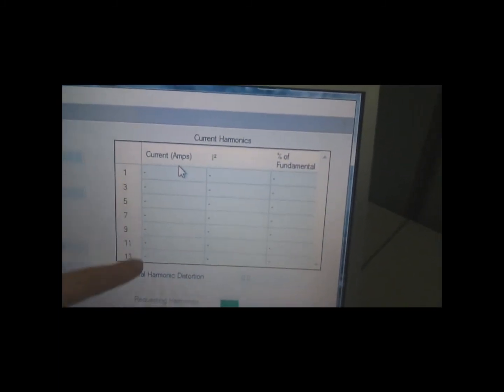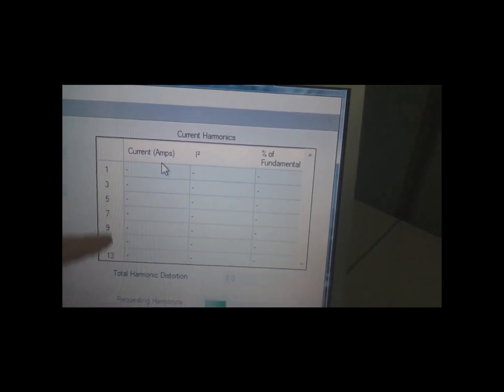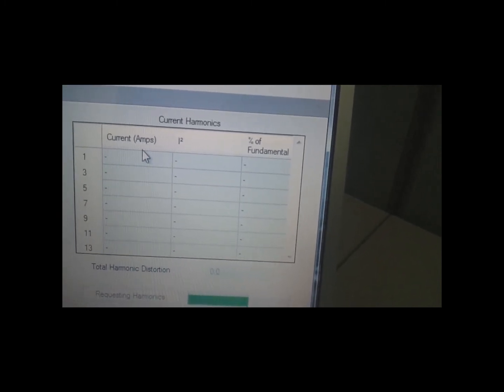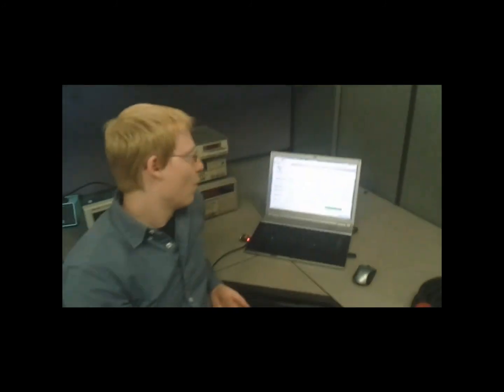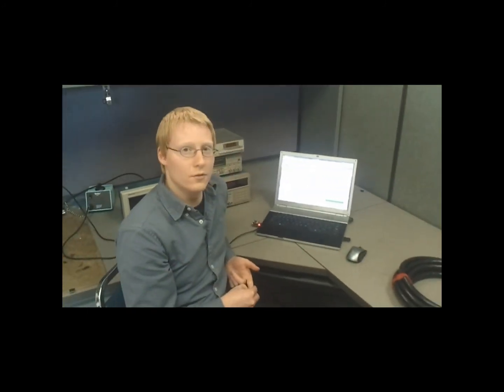On this interface, you see we have the current described in amps for each harmonic, and then the I-squared value so that it's easier to demonstrate the total harmonic distortion, and then we represent the percent of the fundamental harmonic. The reason we calculate harmonics is so we can measure the distortion of the waveform.